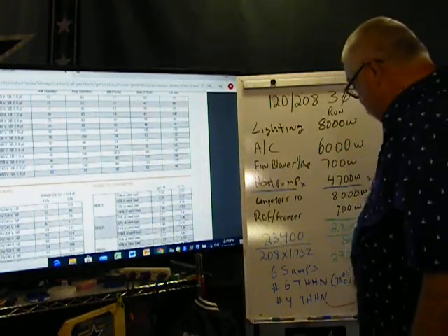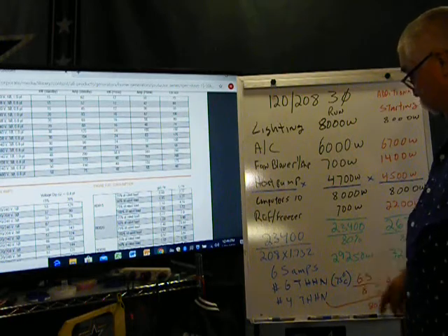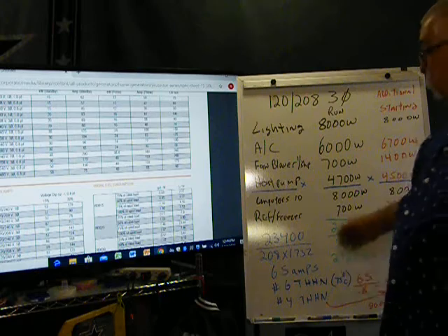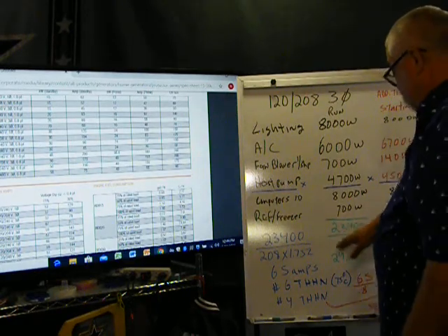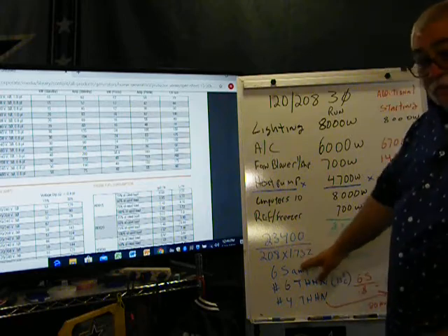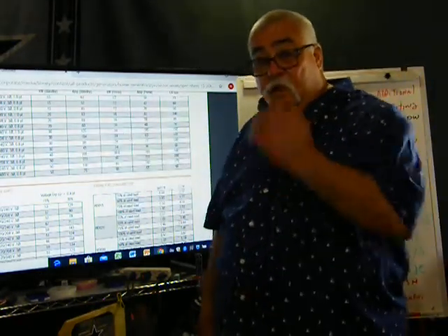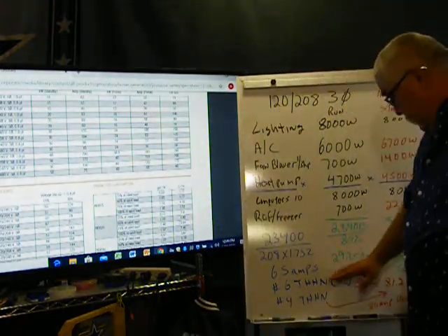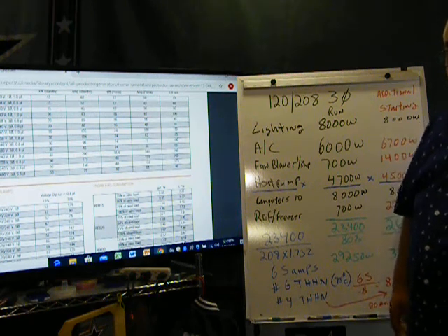Again, because when I did the surge I came up to 29. So if I'm saying I need 29, really can't go by this because this will go at what's there. So you find the amperage, you go to the generators, you can always find it that way. But for right now, if I'm at 29, guess what? I need a 29. I need a 30 kVA. They don't make a 29.